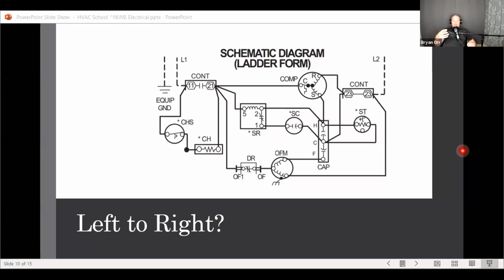And so in some cases, when the valve isn't actually engaging the way it's supposed to, that can actually result in the solenoid coil drawing high amps. But you were correct in that when it happens instantaneously like that, when you have that high current right away and it's actually taking it out, tripping the fuse right away or giving you the big spark, that's an indication that it's actually shorted within the solenoid. Because generally that condition, it's just like if you've ever had a contactor that gets stuck open where it can't engage into the magnet, that will result in high current, but it's not going to be that instantaneous kind of really high.